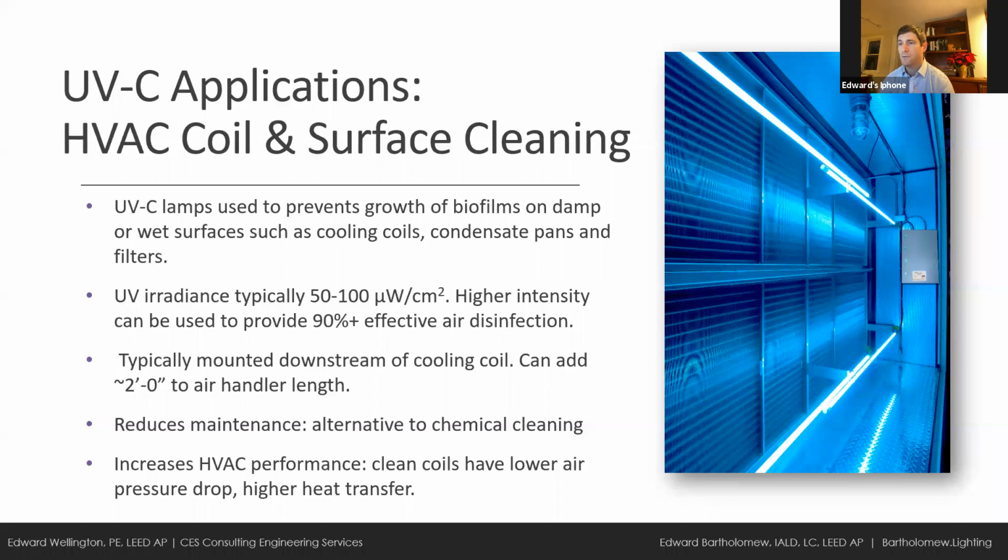And the energy consumption of these lamps is minimal compared to the cost of pushing air through something like a HEPA filter, and also minimal compared to the reduced efficiency and increased maintenance. And if you add in healthcare costs, then these things look really economically attractive. The GSA, the federal agency that maintains all of our federal buildings, actually mandates these in all of their air handling units.